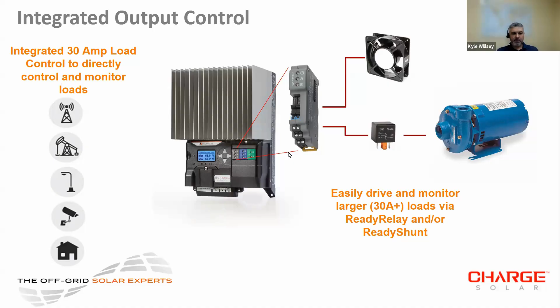If you need to go higher, 30 amps doesn't cover everything, then you can install a Ready Relay that is embedded on a DIN rail that comes with the product to drive a larger relay or a contactor to run a pump or just a larger continuous DC load. That's become a really common use case. There's more to say about the Ready Relay, we'll talk about that in a bit more detail in a moment. But suffice to say, for the purposes of the GenStar, it's a really handy load management option, and you can use multiples to build some fairly complex load management schemes.